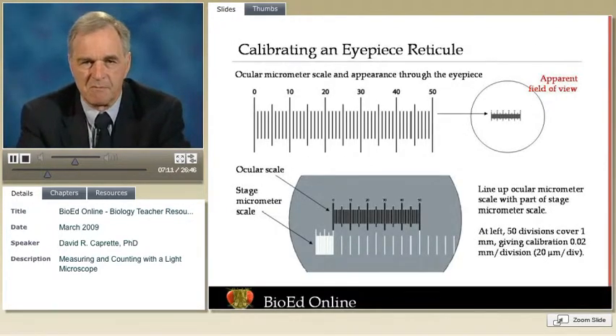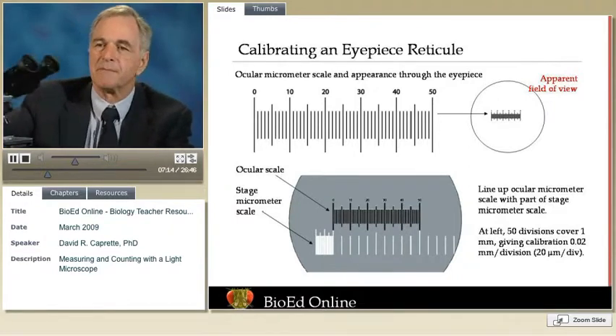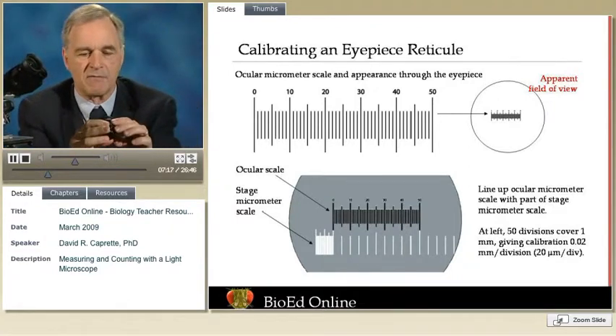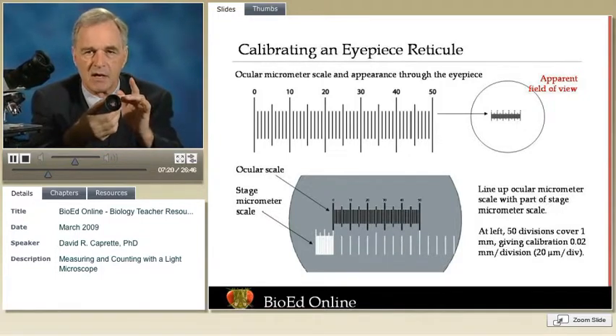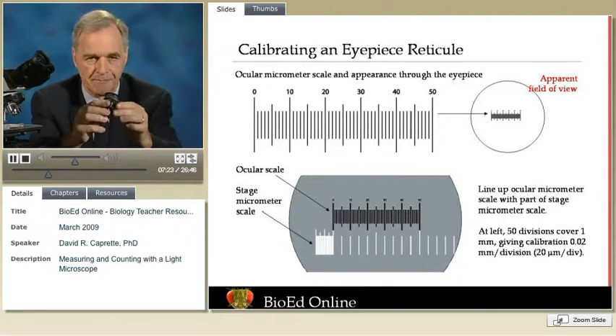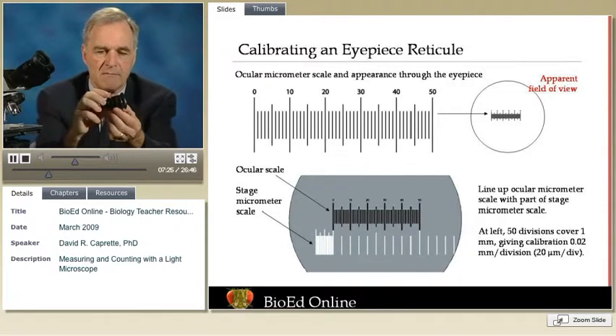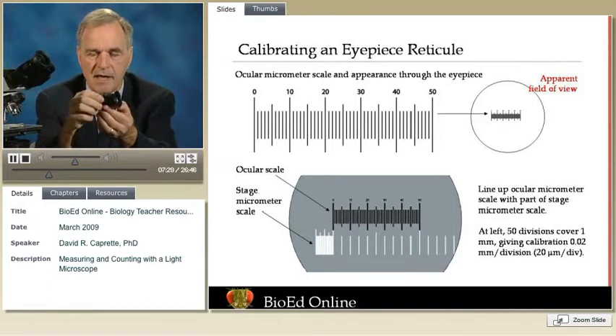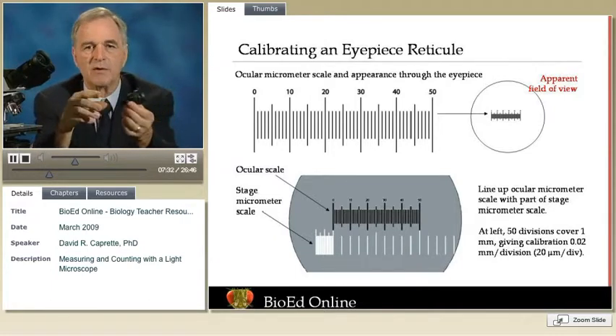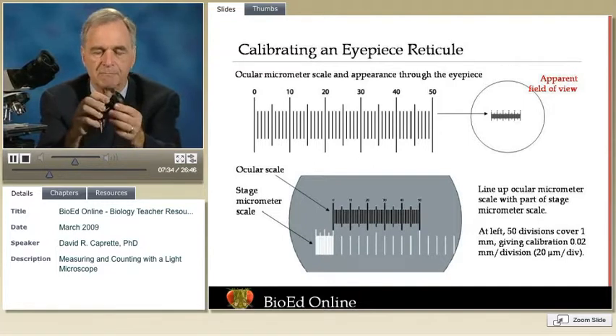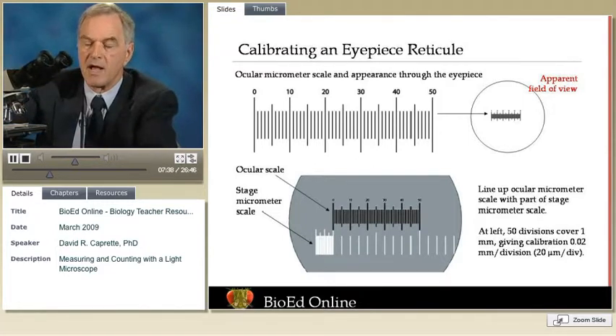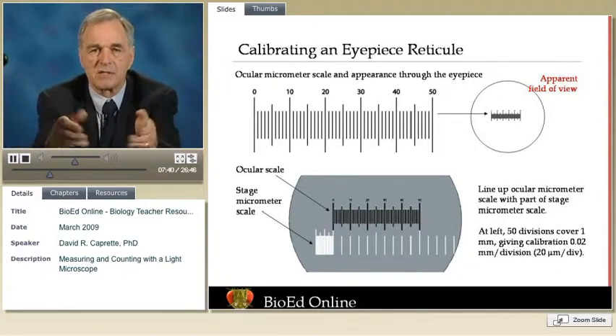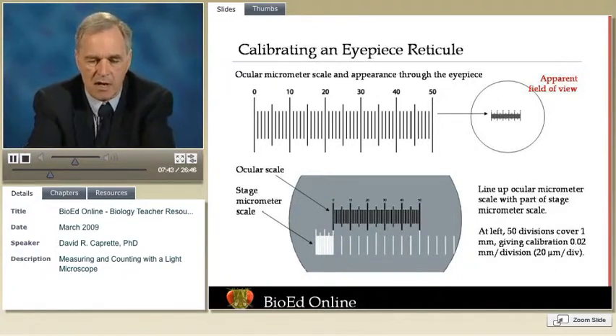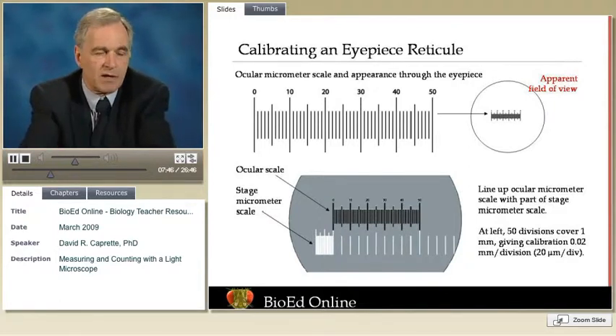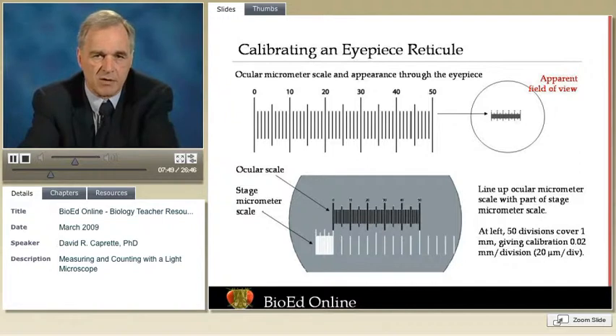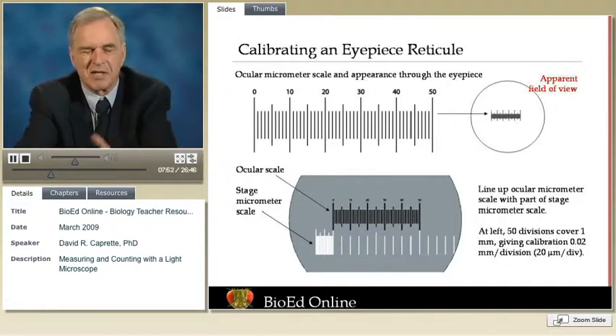If one is to measure dimensions in the XY plane using the microscope, it's necessary to have some sort of scale in the eyepiece or ocular itself. We call such a scale an eyepiece reticle. The reticle can be turned in pretty much any direction by rotating the eyepiece, and the mechanical stage can be moved to line up any object and measure a dimension. But all reticles are not created equal. They vary in number of divisions and in number of divisions per unit length. The calibration of a reticle also varies with the objective lens that you're using. So as you change lenses, you change the calibration.